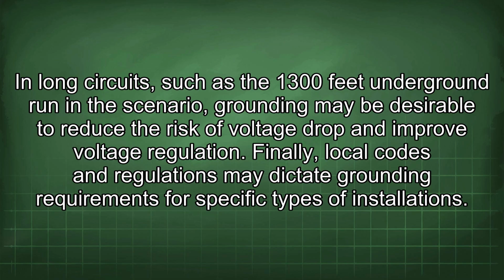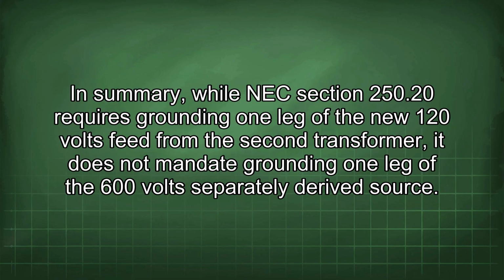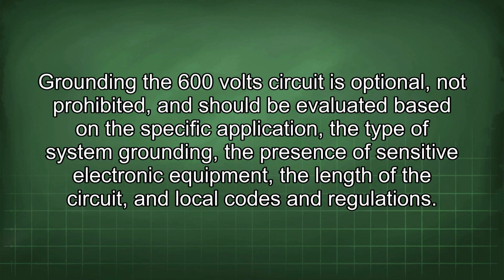In long circuits, such as the 1300 feet underground run in the scenario, grounding may be desirable to reduce the risk of voltage drop and improve voltage regulation. Finally, local codes and regulations may dictate grounding requirements for specific types of installations. In summary, while NEC Section 250.20 requires grounding one leg of the new 120 volts feed from the second transformer, it does not mandate grounding one leg of the 600 volts separately derived source. Grounding the 600 volt circuit is optional, not prohibited, and should be evaluated based on the specific application, the type of system grounding, the presence of sensitive electronic equipment, the length of the circuit, and local codes and regulations.